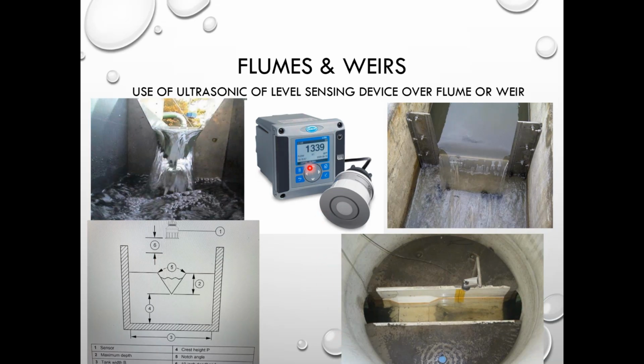Generally it'll come with a transmitter, and you'll have a sensor mounted over the top of the primary device, measuring your liquid depth. With all ultrasonics, they have what we call a dead band. It's an area where the meter will not read, right? So you've got to be aware of the dead band of that sensor. You want at least 6 to 12 inches of space from the bottom of that sensor down to where it reads. This sensor here has a 12-inch dead band. And on your V-notch weirs, you want to make sure you know the notch angle, your crest height, and these dimensions, and these are plugged into the controller. So as it reads level, it correlates that to flow.